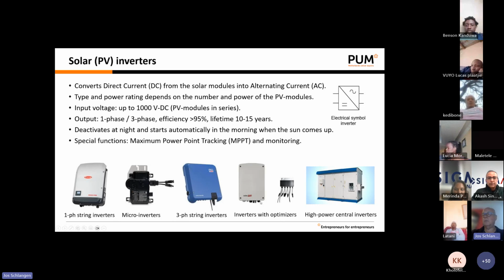Then for the very large systems, either on large buildings or on the ground, you have high power central inverters, which often come in solutions with 20 foot or even 40 foot containers that can be transported to the site as a complete unit. This contains the inverter, the DC cabling and connections, and on the AC side even a transformer to medium voltage and a medium voltage cabinet. So all this can be combined in this central power station.